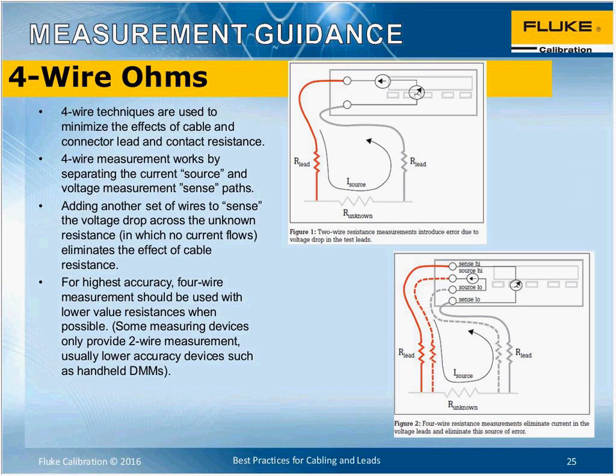Okay, so 4-wire ohms. This is a great feature, and when we're talking about resistance measurements, this is something you should know is a feature you can use with our calibrators. Basically, a 4-wire technique is a way of eliminating the lead resistance in a measurement. What you see there in figure 1, directly out of the application note that I'll send along with this webinar, is that if you were just making a resistance measurement, you have some errors associated with the lead resistance. And depending on the cable or the lead that you're using, it could be significant.